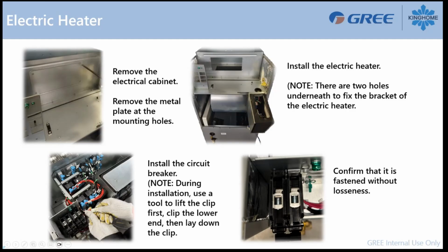When it's done, you can install your duct heater. So the duct heater is in place. You just put 4 screws to hold it in place. You can put back your control board here. Then you will have to attach the breaker. The breaker here comes with the unit.